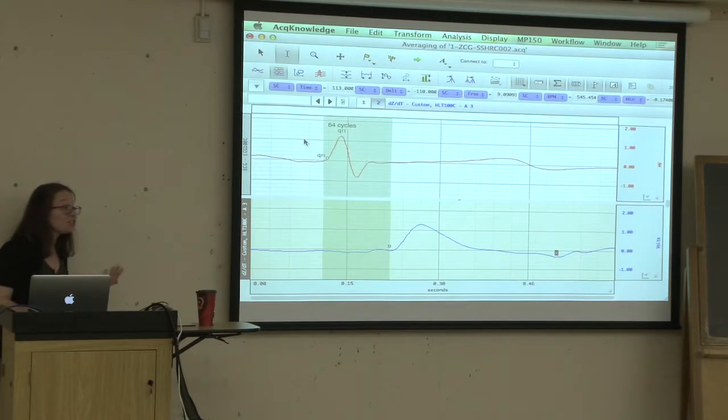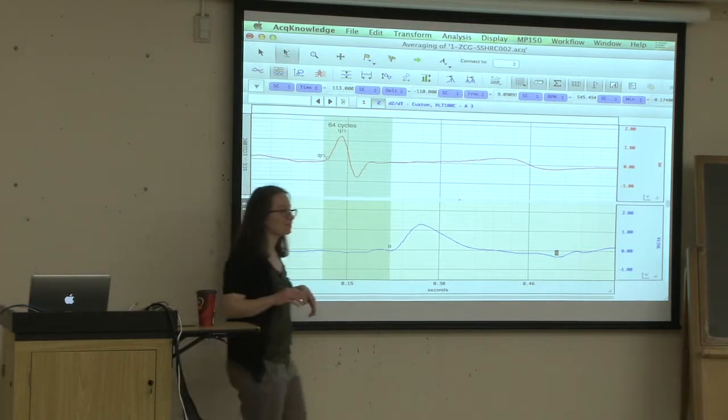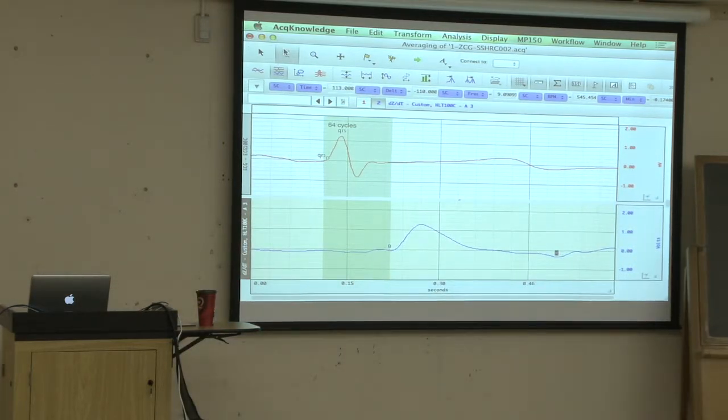So then you go back and do essentially the same thing for LVET. Yes? It says it again? Yeah. So again, I would double check. If you do Control Y, yeah, exactly. If you click, had you clicked on the graph before when you tried it? Click before the first cycle, or just anywhere on the graph with your bar cursor. That might be the difference. And now if you do analysis, find all cycles, it would remember your last default things. Okay, now it's happy.